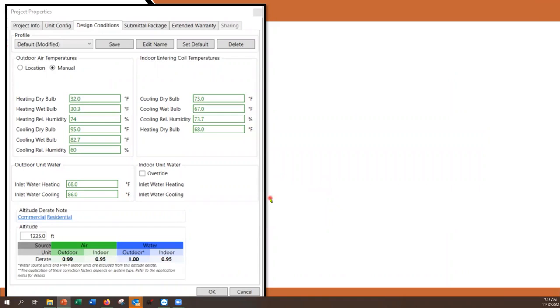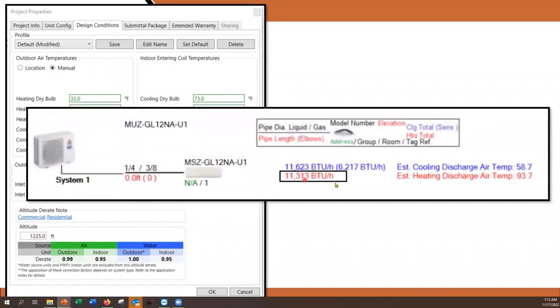Another place to check what this system would possibly output is Mitsubishi's Diamond System Builder. If you're familiar with it, you can put in the actual temperatures that you are experiencing today: the return air temperatures here on the right, outdoor temperatures here, and in this example, 32-degree outdoor air, 74% humidity. I've got an indoor temperature of 68 degrees, and I'm at 1,225 feet of elevation. This is what the Diamond System Builder says I should be getting out of that unit for heat at those conditions. So this is another way, other than just the submittal, to see what the output should be if you really want to be 100% accurate.